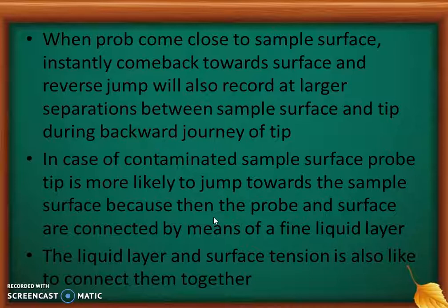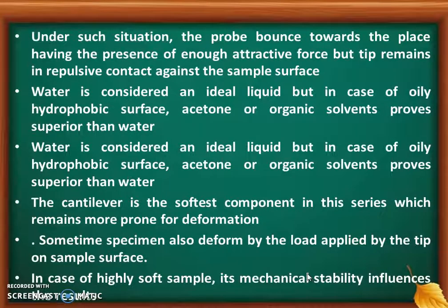In case of contaminated sample surfaces, the probe tip is more likely to jump towards the sample surface because the probe and surface are connected by means of a fine liquid layer. The liquid layer and surface tension also connect them together. Under such a situation, the probe bounces towards the place having enough attractive force, but the tip remains in repulsive contact against the sample surface. Water is considered an ideal liquid, but in case of an oily hydrophobic surface, the organic solvent acetone proves superior to water.